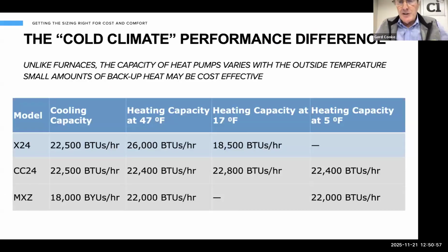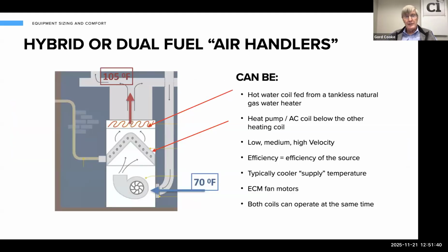So that's pretty critical. Notice the difference here between a standard heat pump, that's the X24 there on the left, and how it shows its heating capacity at 47 Fahrenheit and how it's dropped pretty significantly, even down at 17. And they don't list at all what it'll do at 5 because, frankly, it's turned off. It's not going to run at 5 degrees Fahrenheit, versus the two cold climate heat pumps that are able to keep running, maintain their capacity all the way down to 5 Fahrenheit, and keep running past that. They're not cutting off at 5. And therefore, only small amounts of backup heat are needed. Sometimes you can do it entirely with the heat pump. Sometimes you need a little bit of backup heat. So what do you do for backup? Well, there's the heat pump on the left.